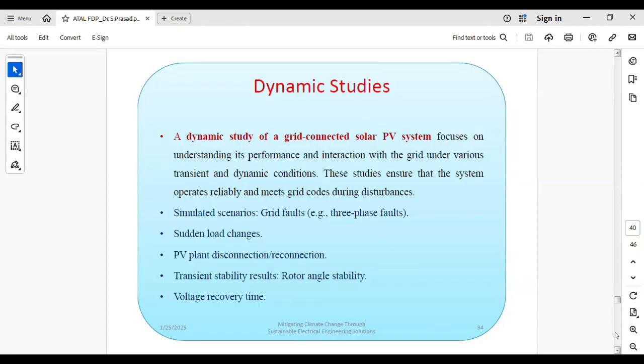Therefore you need to perform rotor angle stability, to check whether the rotor angle of the generators is within 0 to 90 degrees or not. When the three-phase fault happens, at what time you remove the fault matters. That is the critical clearing time, CCT, the fault clearing time we are calculating: when a three-phase fault has happened at a transmission line, at what time we should remove the fault so that the generator will not become unstable.